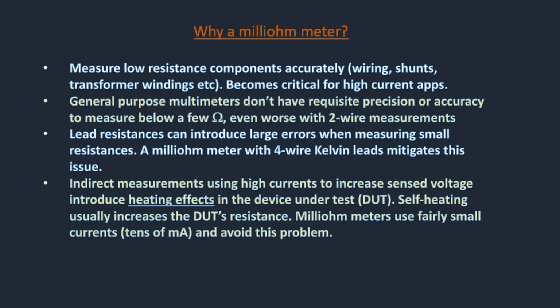A milliohm-meter typically will have 4-wire Kelvin leads, which mitigates this issue. And lastly, if you try to do it indirectly by pumping a lot of current into the device under test, it will usually heat up and it will increase the resistance, most likely causing errors. So you want to avoid these kind of problems.